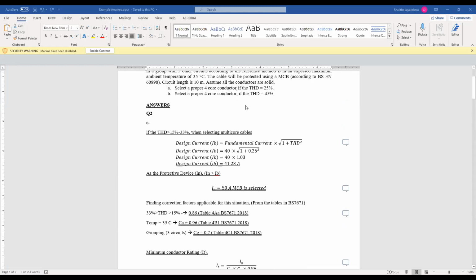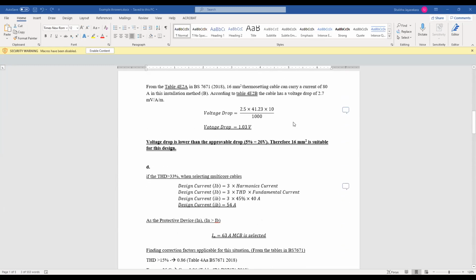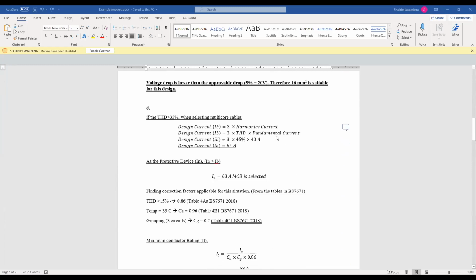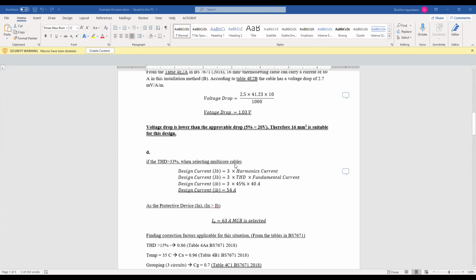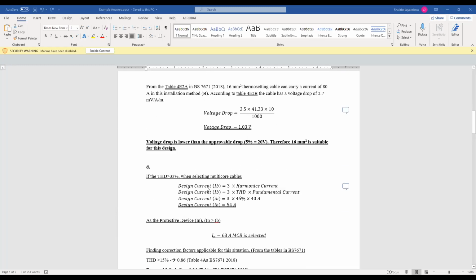So now in the second part it says do this design again for THD value of 45%. So in here, if your THD value is higher than 33%, you have to base your design on the neutral current. So I think I showed that to you earlier. So in here your THD is 45%. So your design current will be 3 times the harmonic current, because now your harmonic current is more dominant. So if it is 45%, 45% into 3 means about 135%, right?